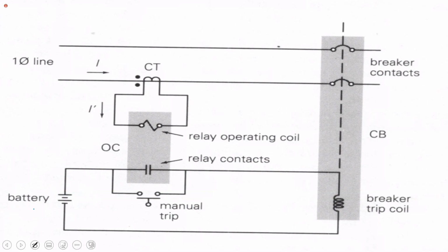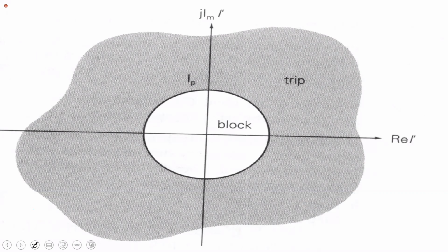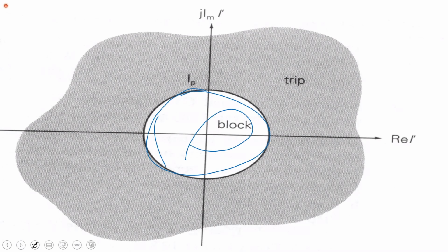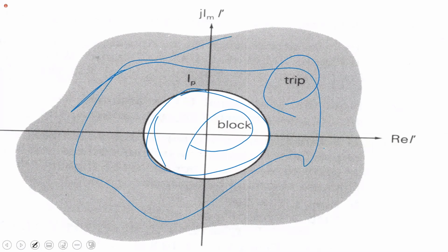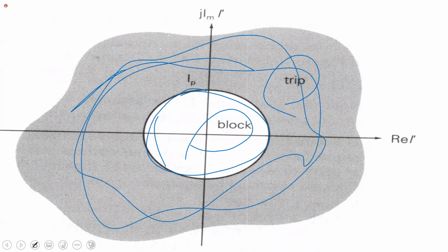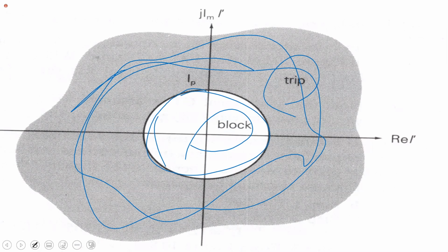But anyway, I digress. So here is the operating space for your overcurrent relay. Once the current is below a certain value, then it is blocked. Once it's above a certain value, then it trips. So anything outside here should cause it to operate. And let me say operate, because this is the relay. The tripping really takes place on the part of the breaker. All right?